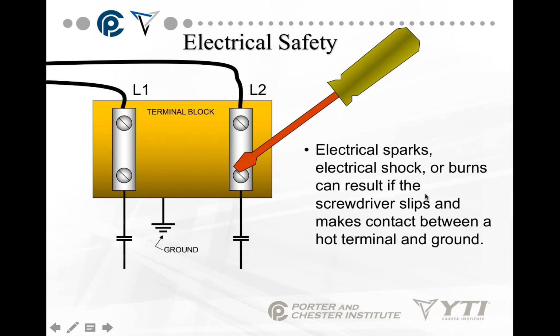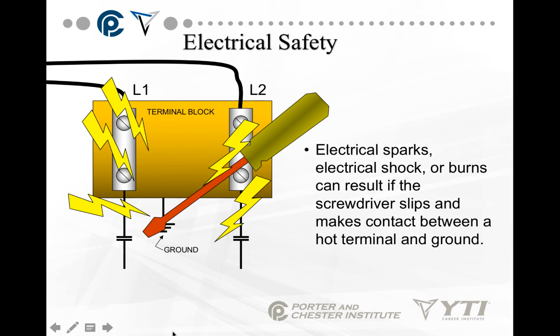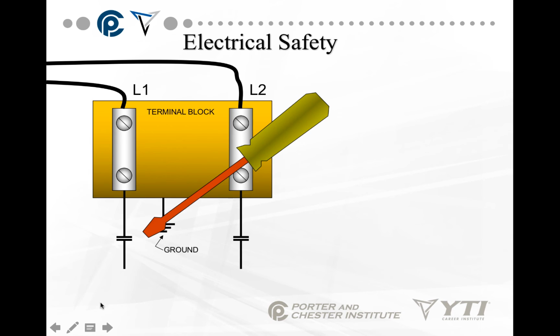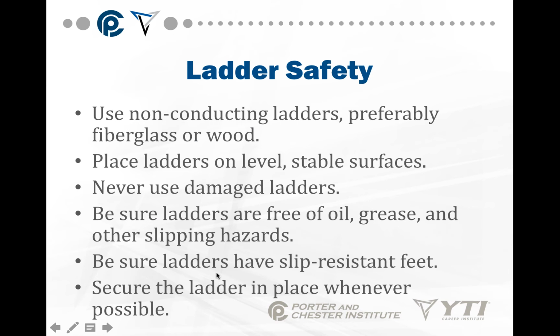Electrical sparks, shock, or burns can result if the screwdriver slips and makes contact between a hot terminal and ground. So anytime you're working with a screwdriver, like unscrewing or rescrewing something in an electrical panel, turn the power off, because those sparks can actually cause a lot of problems.